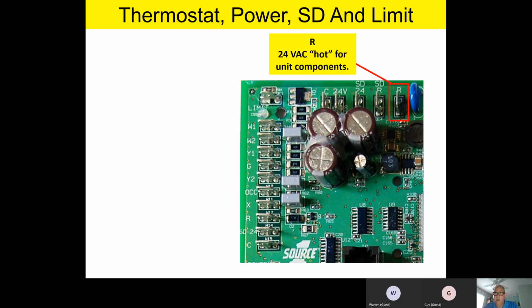Right next to that is an R output. This is an auxiliary 24-volt output, 24-volt hot for other unit components. So from the factory, you may see something hooked up to that R terminal, or it may just be open. Based on the tonnage of the unit and so on, you may or may not have anything hooked up to that from the factory.